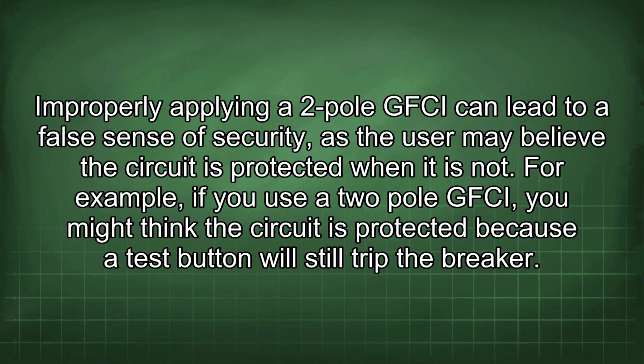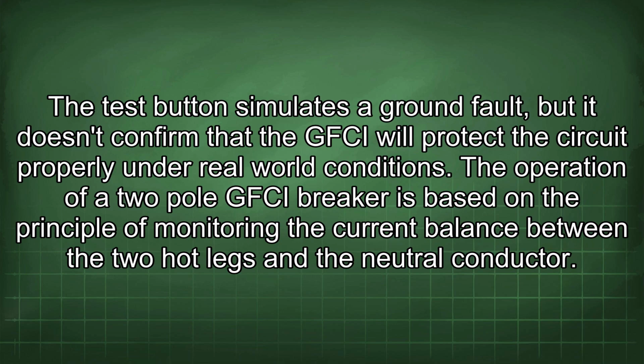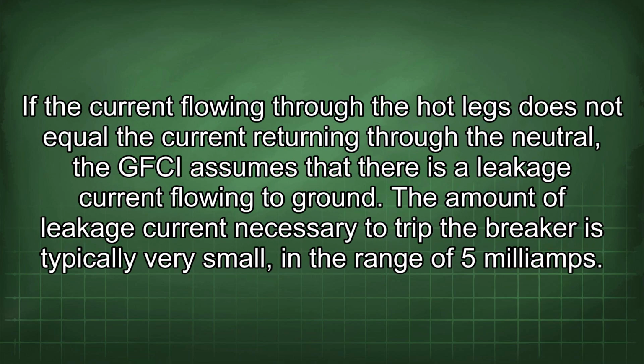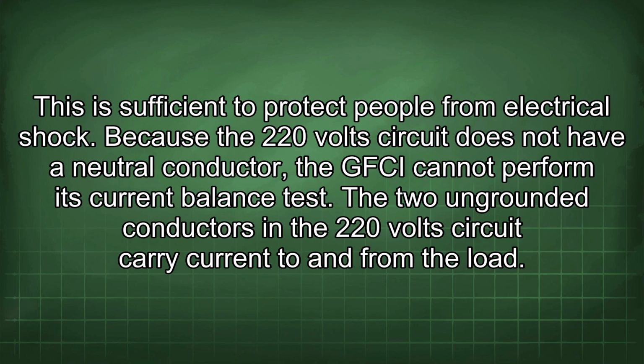For example, if you use a two-pole GFCI, you might think the circuit is protected because a test button will still trip the breaker. The test button simulates a ground fault, but it doesn't confirm that the GFCI will protect the circuit properly under real-world conditions. The operation of a two-pole GFCI breaker is based on the principle of monitoring the current balance between the two hot legs and the neutral conductor. If the current flowing through the hot legs does not equal the current returning through the neutral, the GFCI assumes that there is a leakage current flowing to ground. The amount of leakage current necessary to trip the breaker is typically very small, in the range of 5 milliamps. This is sufficient to protect people from electrical shock.